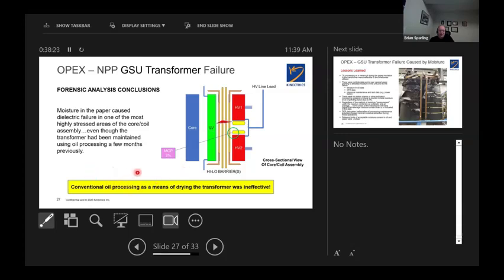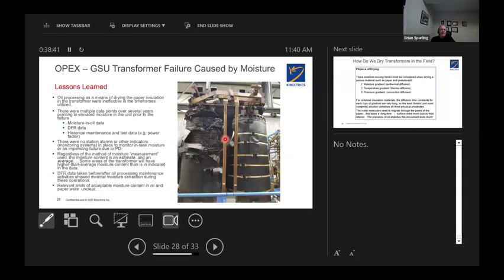They had used the conventional oil processing and means of drying the transformer, but it was ineffective because you just dried the oil. You didn't dry the paper. And the moisture content in the paper, as determined by doing all the samples in the lab, was at 3% in this area. And you had this impact. So the oil processing as a means of drying the paper insulation was ineffective in this time frame. And looking over the previous data, there was no online monitoring on this transformer. Looking over the data over time was a bit confusing for some people. They really didn't understand what they were looking for.